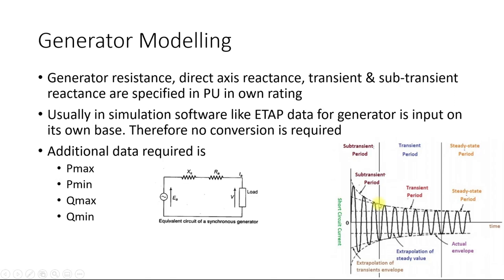After a few cycles, the fault current is reduced and the generator enters into a transient period. During this period, the short circuit is limited by transient reactance. And ultimately, after many cycles or many seconds, the generator reaches its steady state period, during which the reactance is known as the steady state reactance or synchronous reactance.